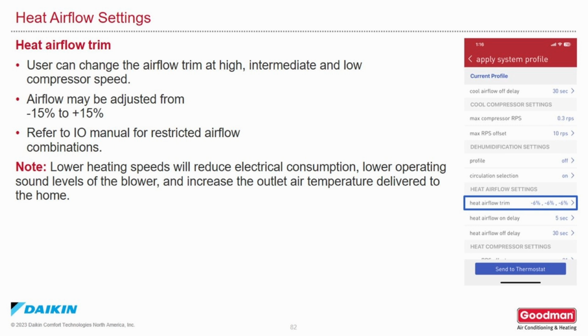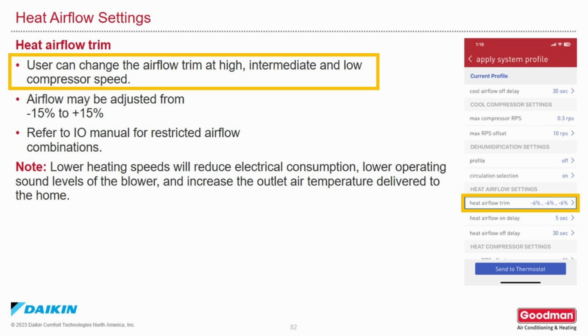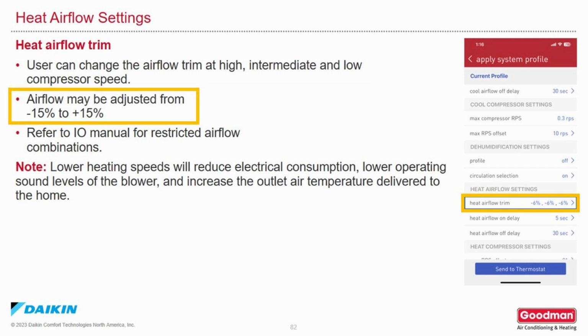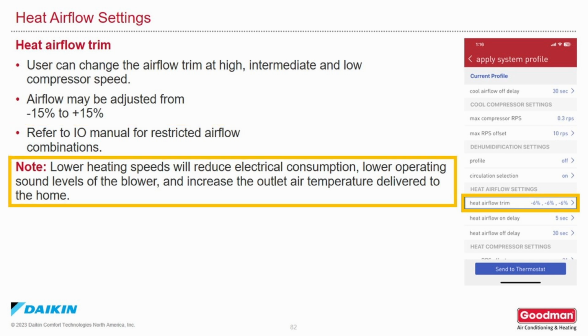For heating airflow settings, the user can change the heating airflow trim at high, intermediate, or low compressor speed. Airflow may be adjusted from -15% to +15%. Refer to the IOM for restricted airflow combinations. Please note, lower heating speeds will reduce electrical consumption, lower operating sound levels for the blower, and increase the outlet temperature of the air delivered to the space.